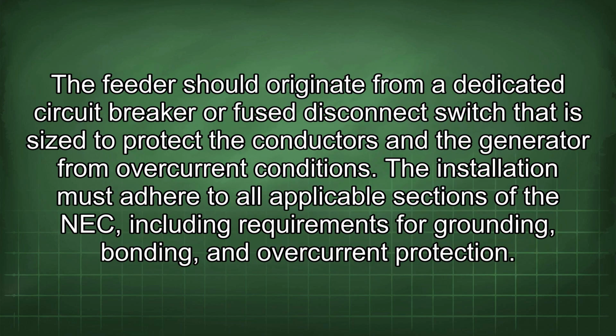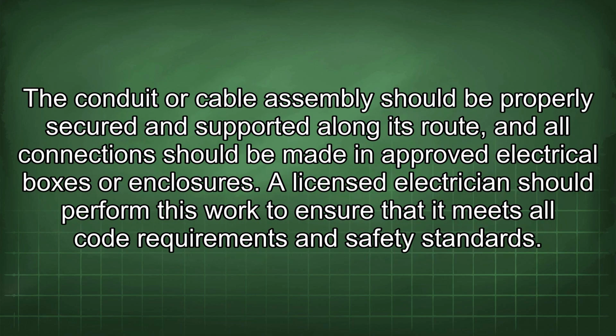The feeder should originate from a dedicated circuit breaker or fused disconnect switch that is sized to protect the conductors and the generator from overcurrent conditions. The installation must adhere to all applicable sections of the NEC, including requirements for grounding, bonding, and overcurrent protection. The conduit or cable assembly should be properly secured and supported along its route, and all connections should be made in approved electrical boxes or enclosures.